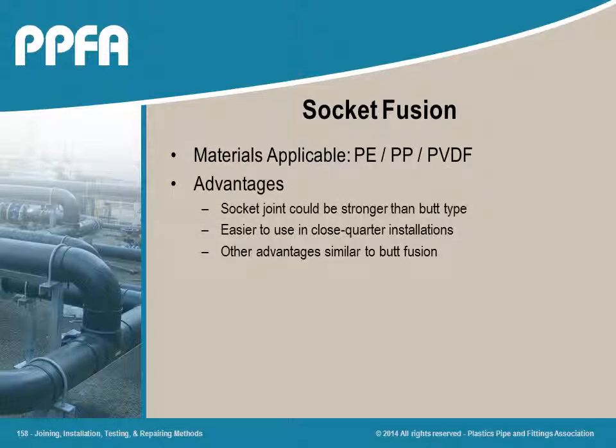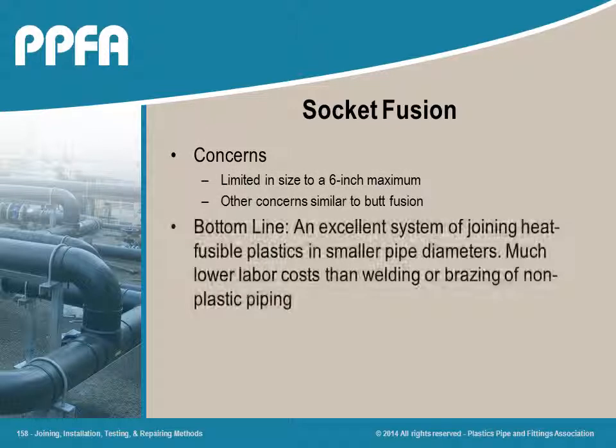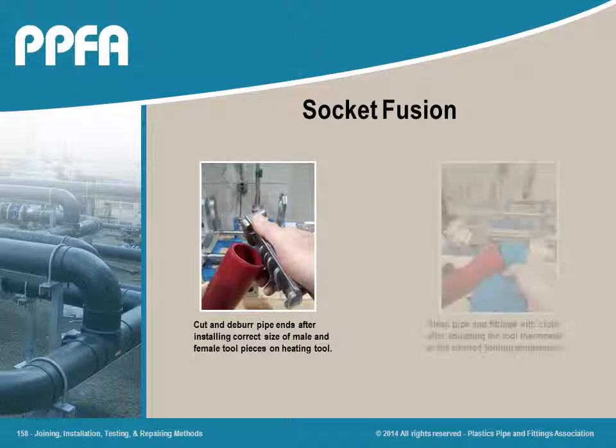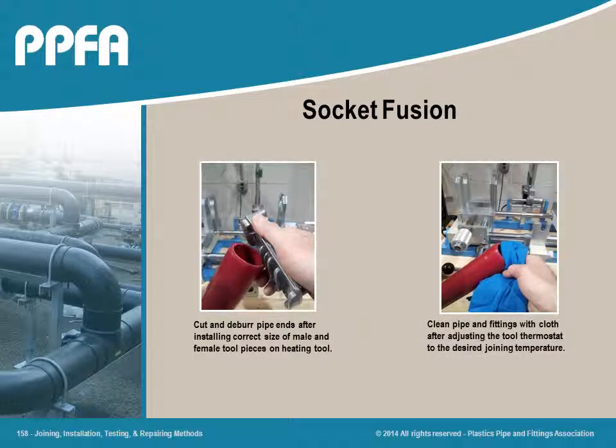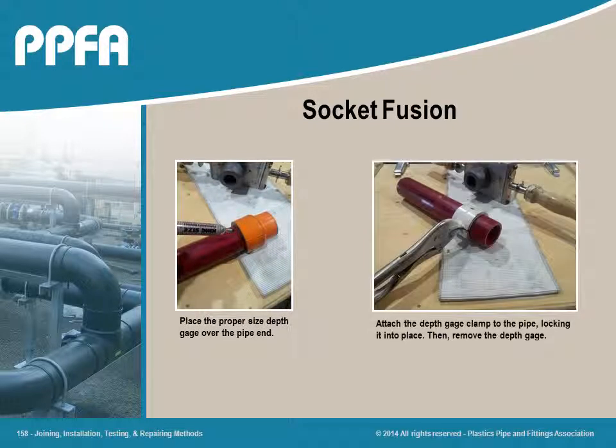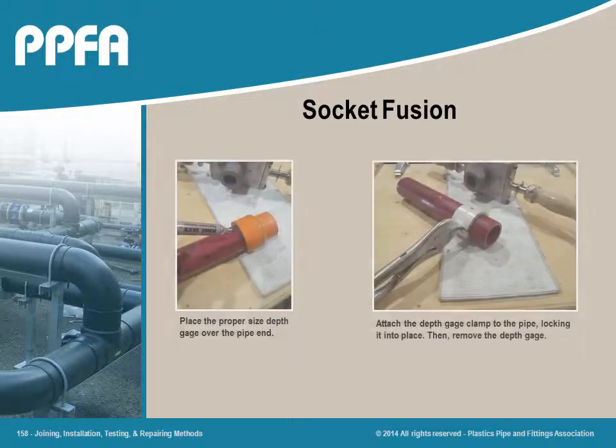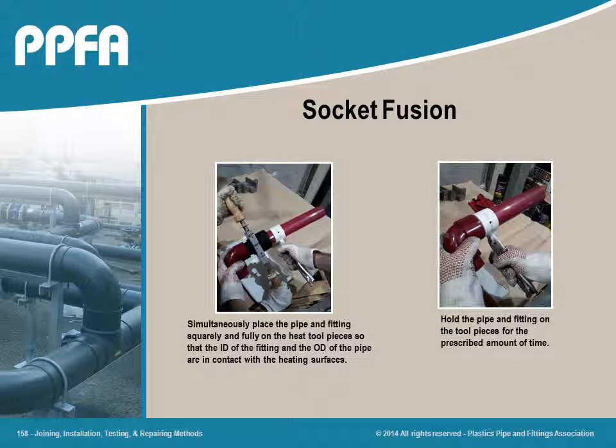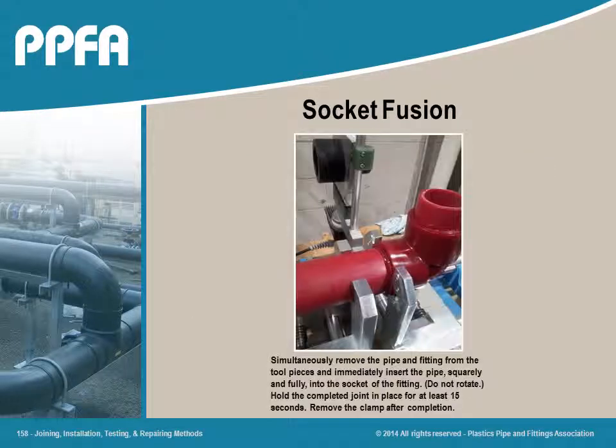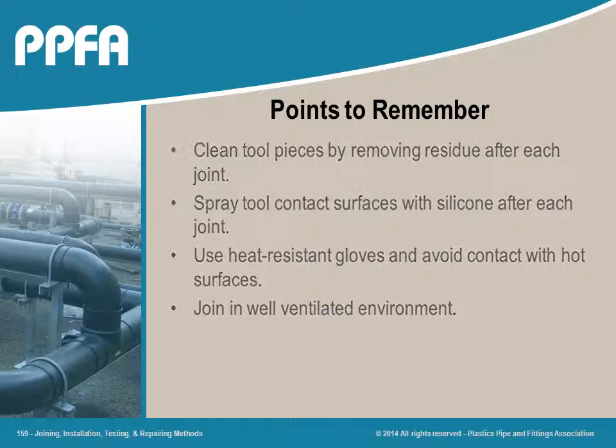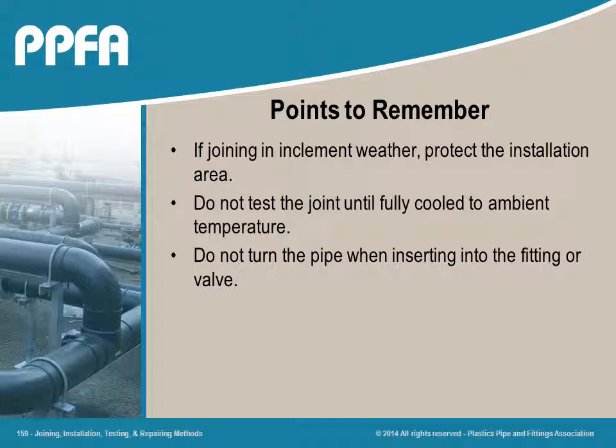Socket heat fusion joining systems have been successfully used for over 4 decades. Socket fusion requires heating the pipe OD and the fitting socket, then assembling while the material is still soft. The heat soak time can be visually controlled by observing the diameter of the bead against the heating tools. The final joint will have a similar size bead as in butt fusion. This joining system is ideal for pipe diameter 6 inches and below and for close quarter installations. As in all heat fusion joining methods, be conscious of working with the hot plate. Insulated gloves should be used for safety reasons.